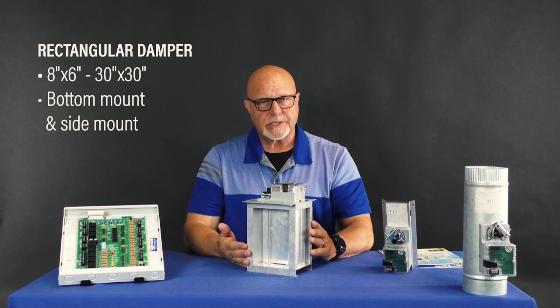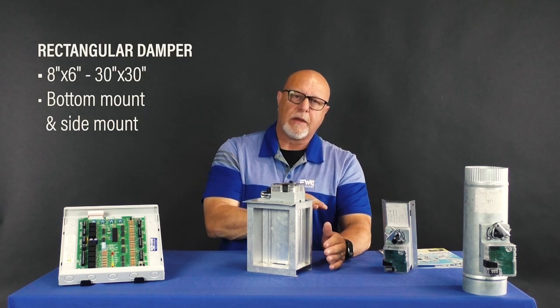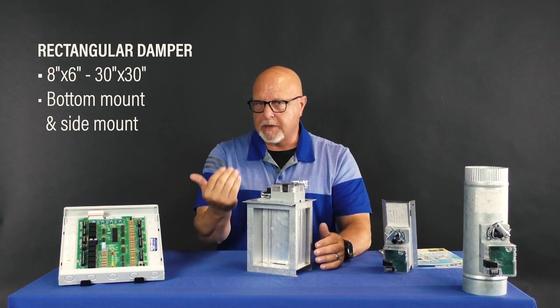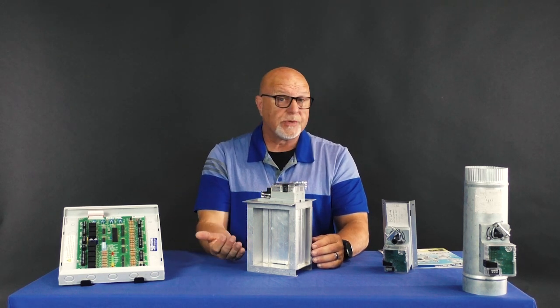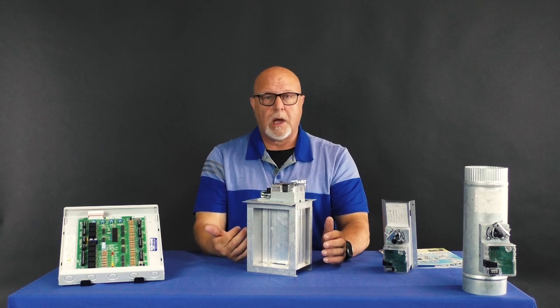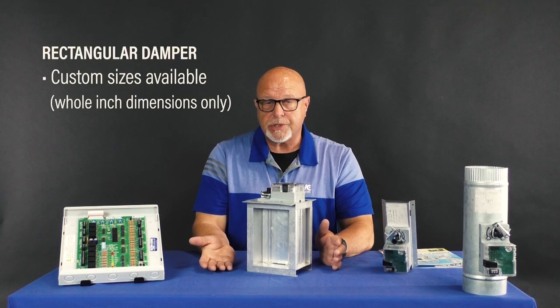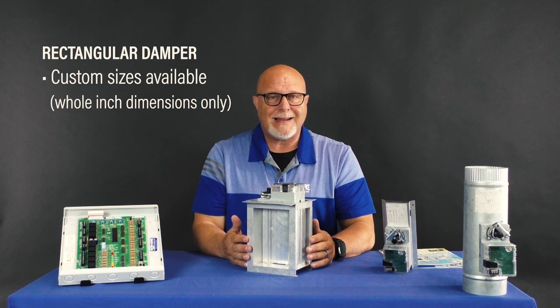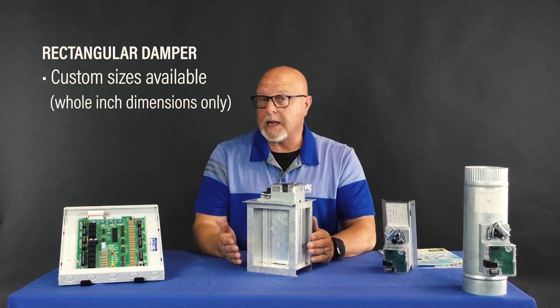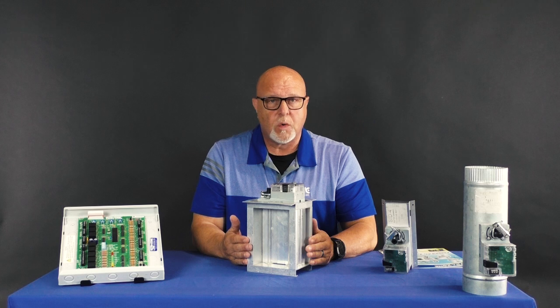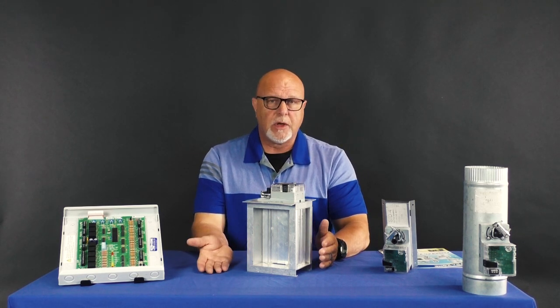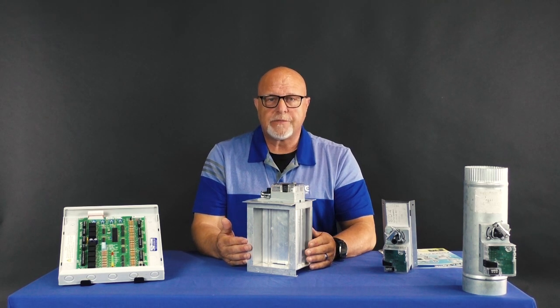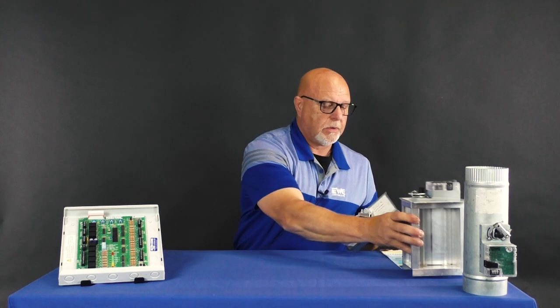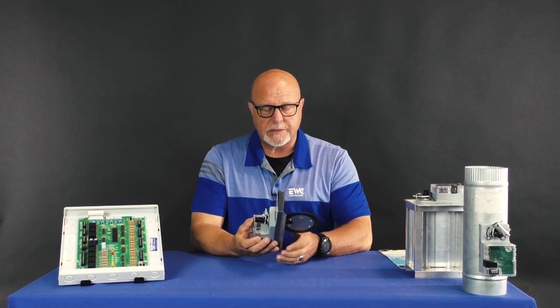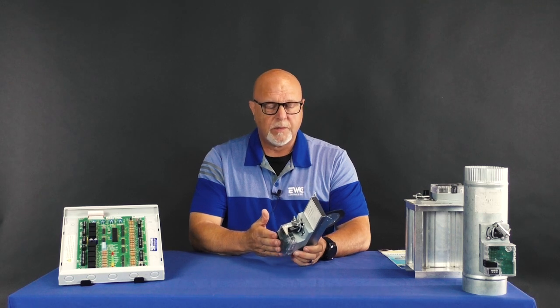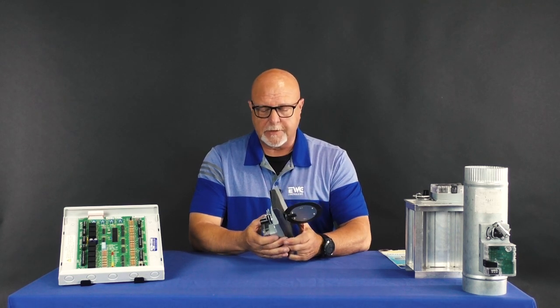Again, I make this 8x6 through 30x30, both bottom mount and side mount. And if the contractor needs a special size, we make those on the inch. So meaning I'm not going to make a 19.5. I'll make a 19. But I won't make a 19.25 or 19.5. We can ship those usually 3 days from receipt of order. Moving along to our retrofit damper, again, that's the same actuator as all the rest of them, with the same features and benefits that I went over earlier.